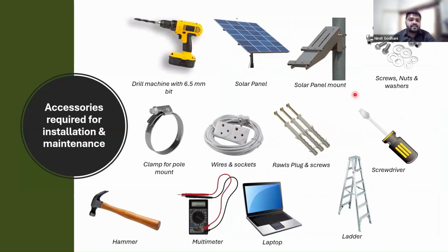Some accessories are also required for the installation team. When we send our technician into the field for routine maintenance or troubleshooting, we make sure that these devices are with them, so there is no need to worry at the time of installation. They will carry mostly a laptop and multimeter. They are the must priority. They will check the power supply, the sensors, and the laptop for connectivity and for recorded measurements into the SIM card.